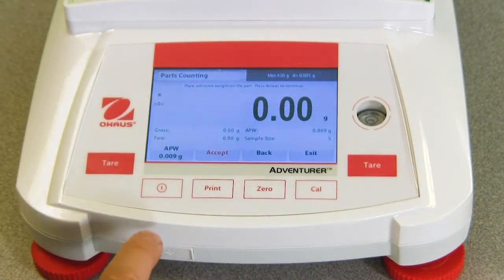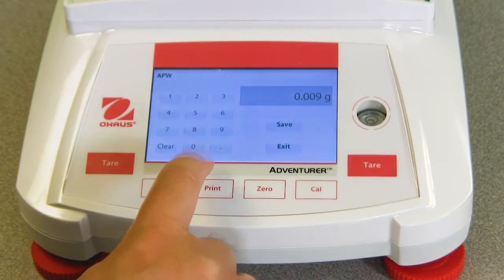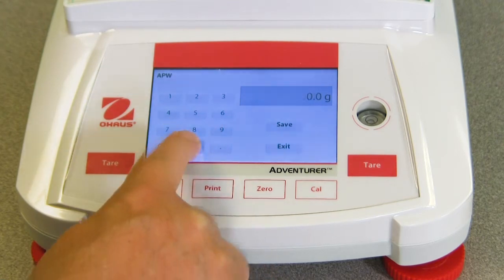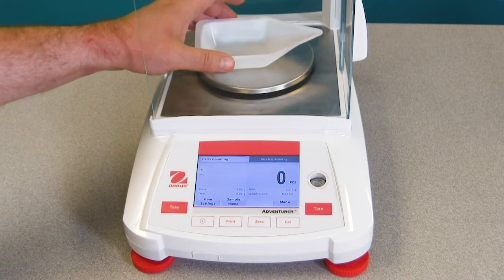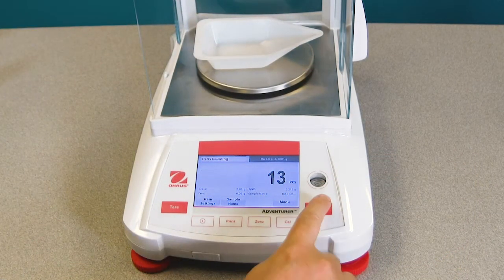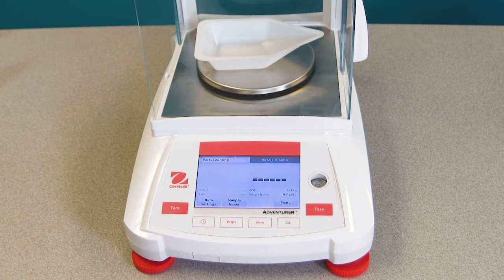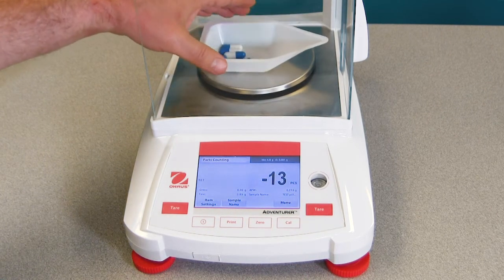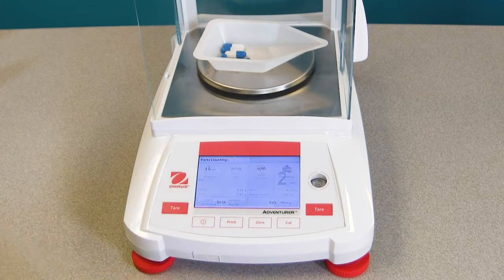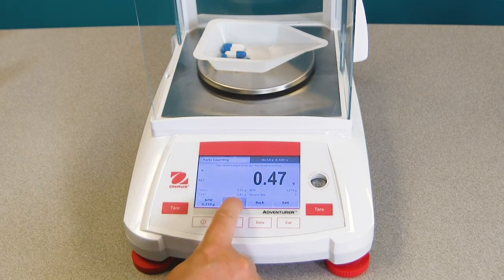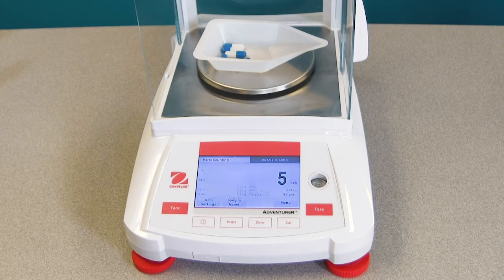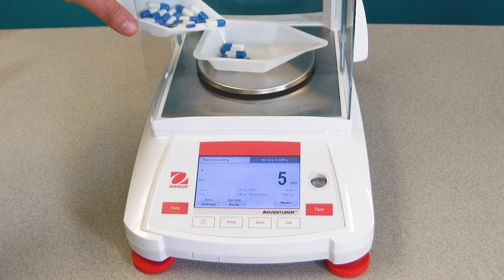When running the parts counting application on the balance, there may be times when you need to change the average piece weight. The easiest way is to place the container on the pan and then tare. Add a sample unit and press the APW button. Then press Accept. The display will then return to the Parts Counting application home screen with the new APW value.